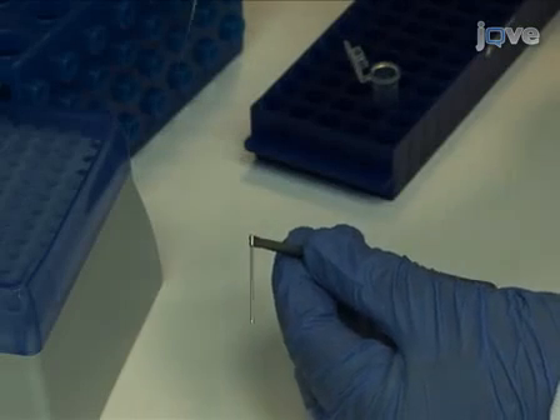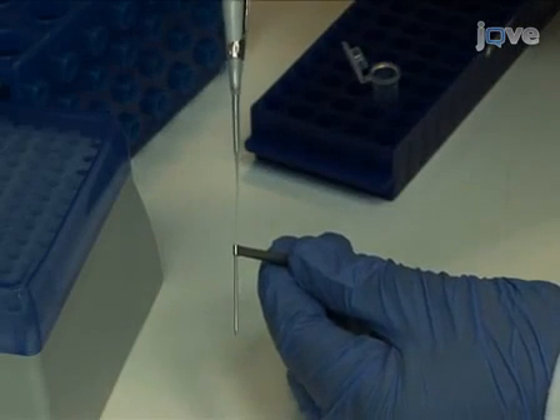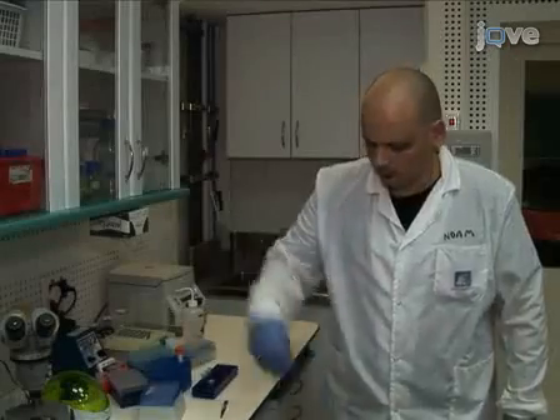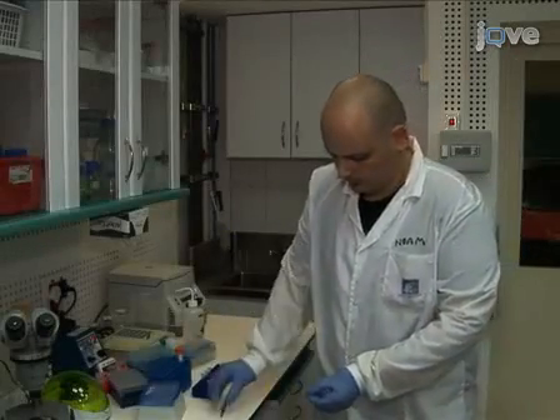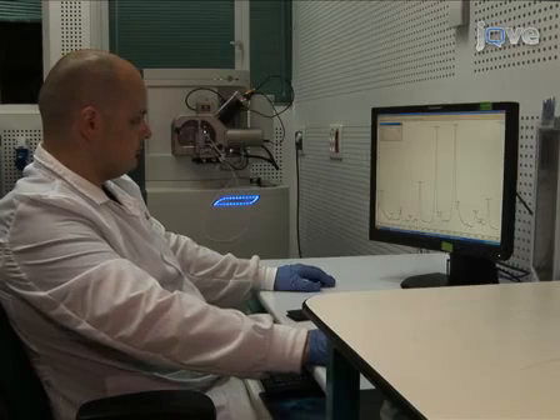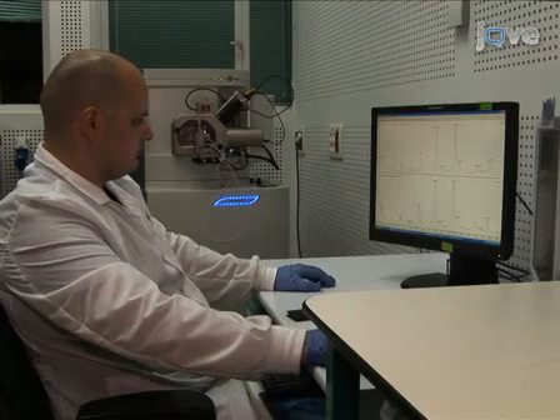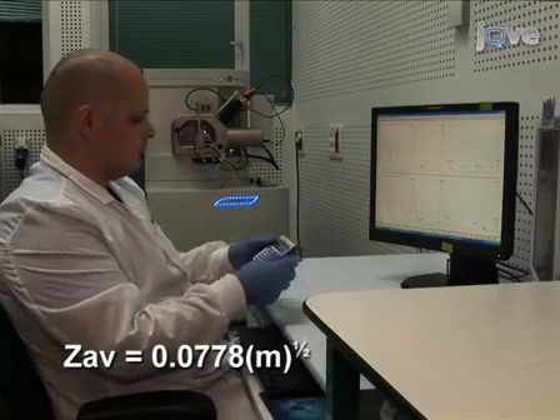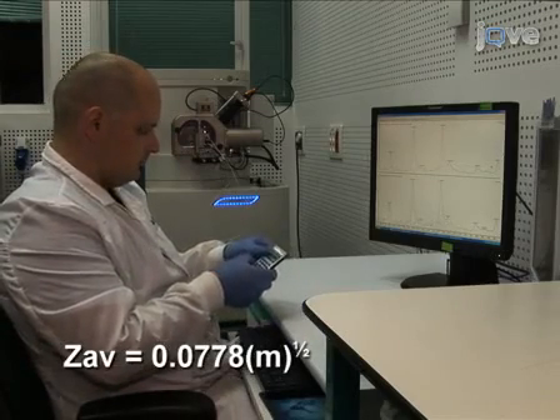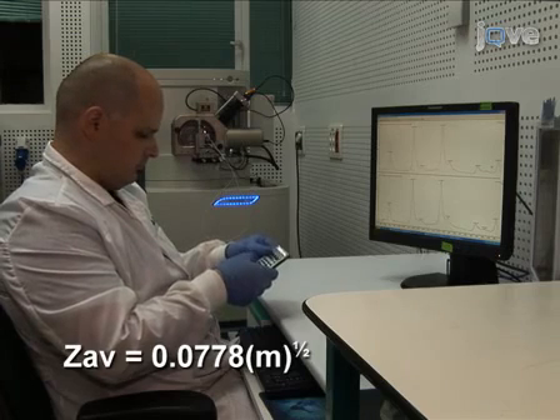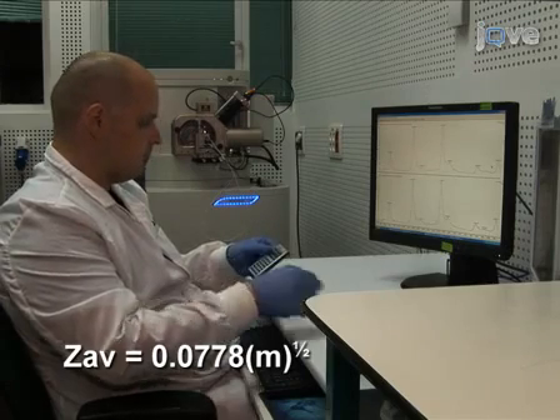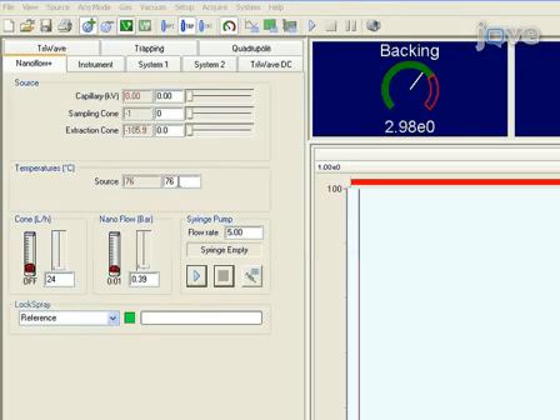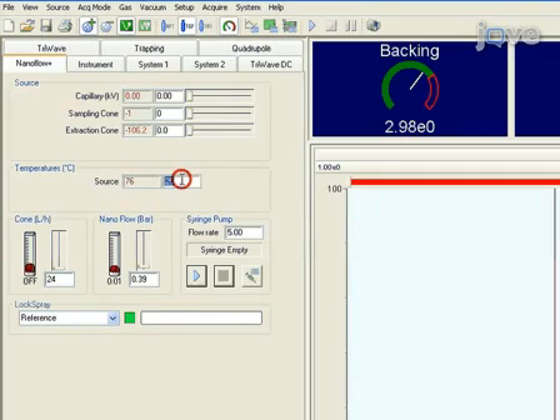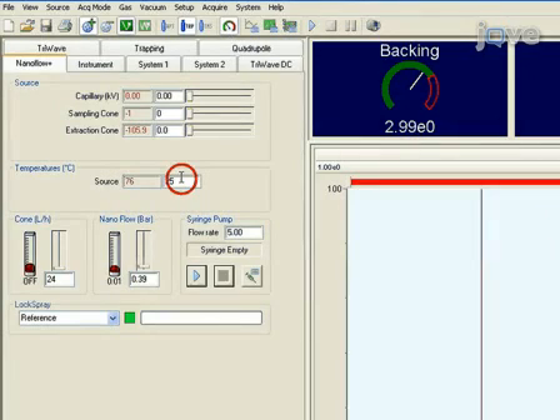Next, load the sample as shown for the cesium iodide calibration and initiate spray. Start by initial optimization of the spray until the signal is detected. Use the equation for average charge state shown, in which m is the mass of the complex in Daltons. However, the exact position of the charge states is protein dependent. To prevent complex dissociation, do not heat the ion source. Either switch the heater off or keep the temperature below 40 degrees Celsius.